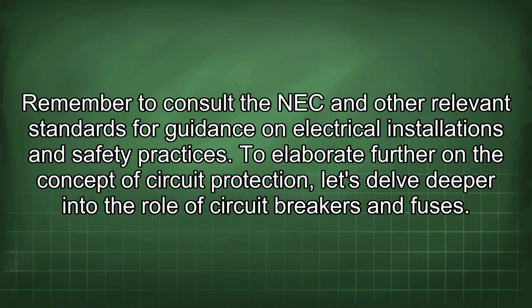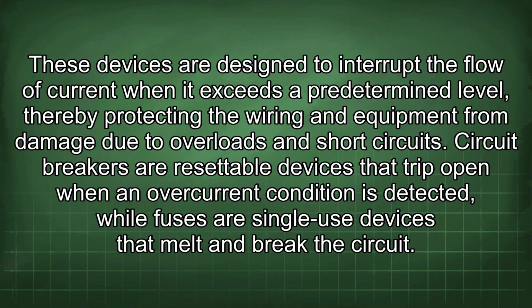To elaborate further on the concept of circuit protection, let's delve deeper into the role of circuit breakers and fuses. These devices are designed to interrupt the flow of current when it exceeds a predetermined level, thereby protecting the wiring and equipment from damage due to overloads and short circuits. Circuit breakers are resettable devices that trip open when an overcurrent condition is detected, while fuses are single-use devices that melt and break the circuit.